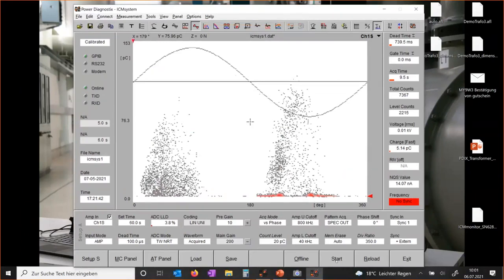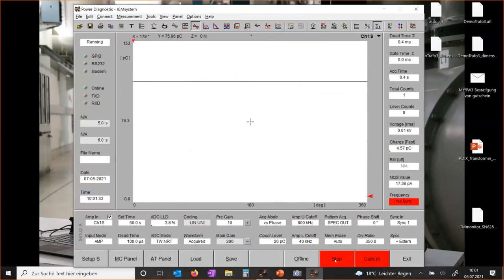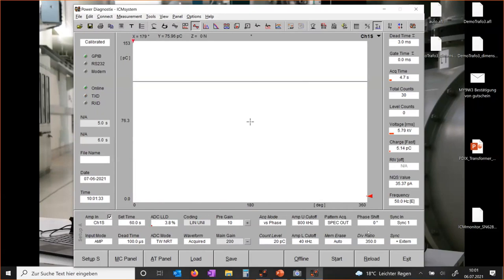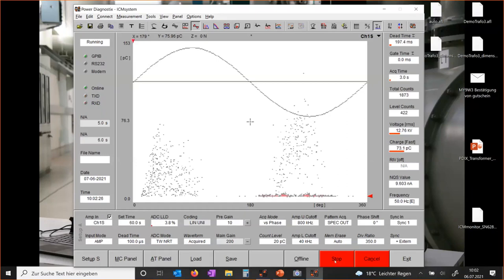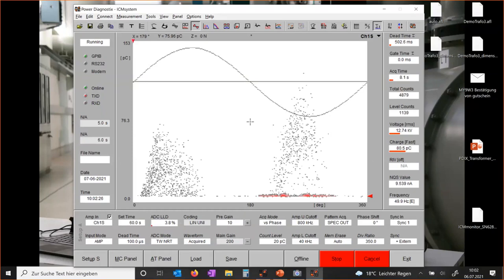Currently there's no voltage applied, so we're recording an empty pattern. I'll now switch on the voltage and raise it to a value where I know there is PD. The voltage is now at 5.8 kV and I'll raise it toward 13–14 kV. You can now see in the window below that there is PD activity — very good.